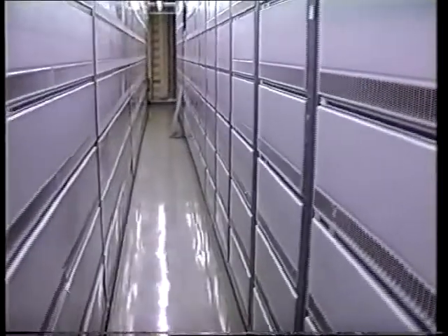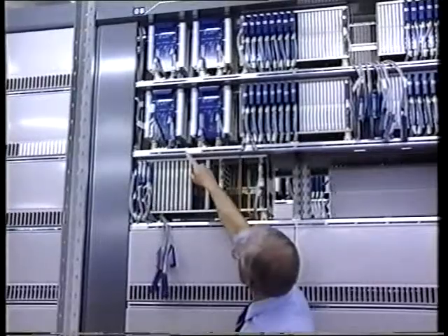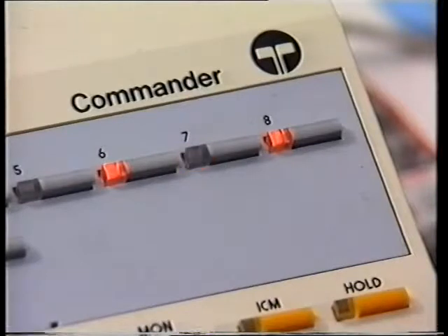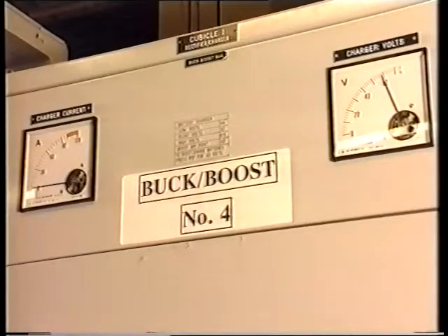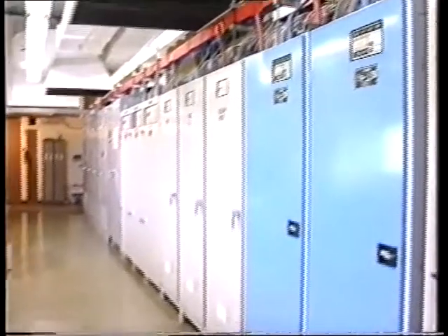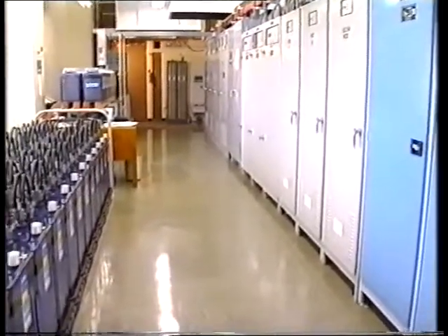Buck-boost power supplies were introduced initially to serve early AXE, stored program controlled telephone exchanges. Since their inception, a number of outages have occurred due to a lack of understanding and subsequent misoperation of this equipment. These outages, in most cases, have been severe, resulting in lost revenue and a large number of customers being affected. Let us now examine the buck-boost power supply system by first comparing it with alternative power conversion systems and then explaining its modes of operation in some detail.